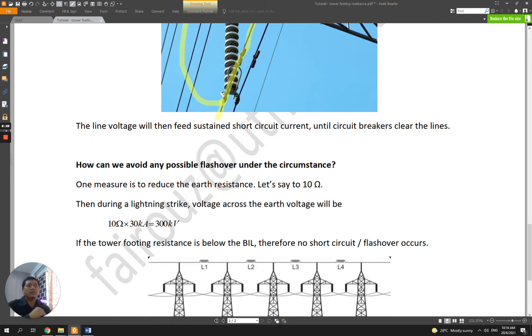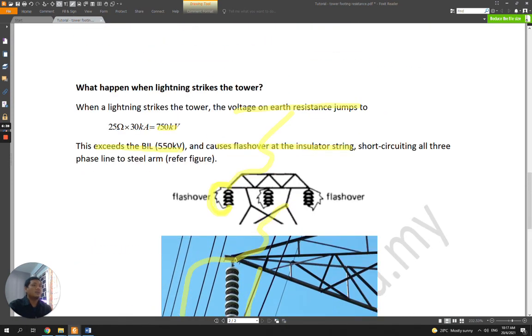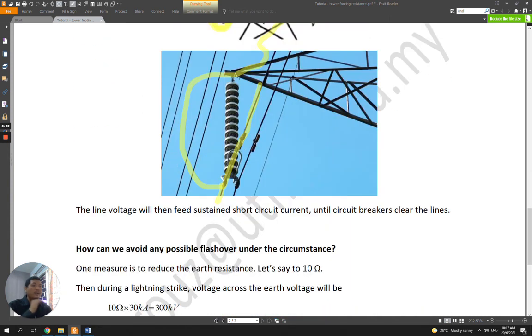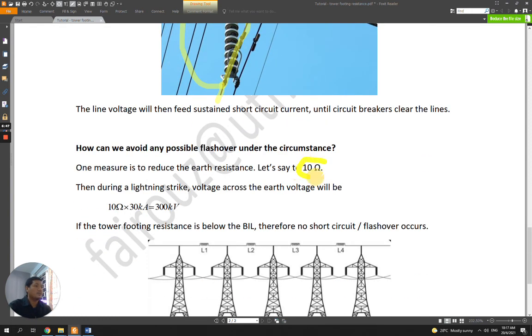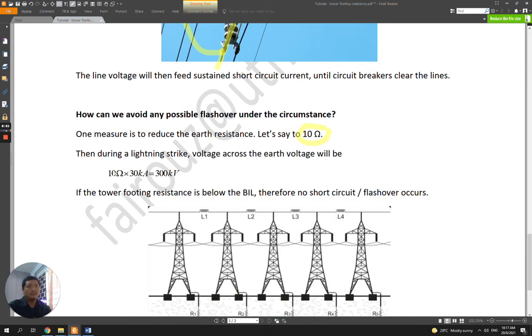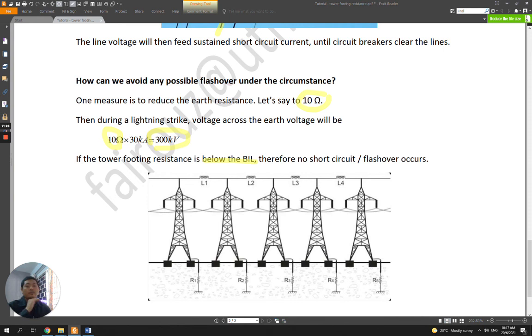So how can we avoid any possible flashover under this circumstance? One measure is to reduce the earth resistance, or the tower footing resistance. Now the tower footing resistance is 25 ohms. What happens if we reduce it to 10 ohms? Let's say 10 ohms. We'll do the calculation again. If the tower footing resistance is 10 ohms, multiplied with the same lightning, 30 kiloamp, we get a voltage of only 300 kilovolt due to the lightning strike. You can see that this is below the basic impulse lightning level. There is therefore no short circuit or flashover.